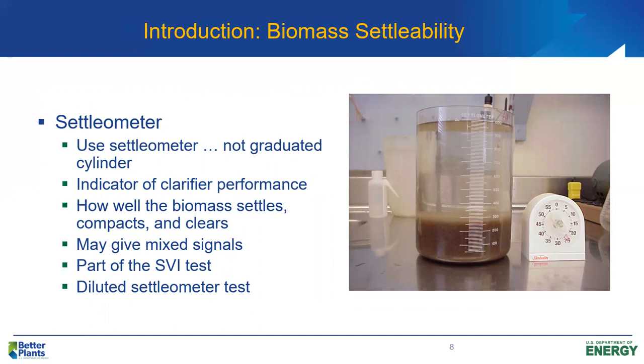If you were to ask me which single tool I'd choose to operate an activated sludge plant, I'd say give me a settleometer and I could probably do a reasonably good job. Obviously we want to use all the tools in our toolbox — like a doctor who should run whatever tests are needed, not just one. But the settleometer test is really valuable. It tells us a lot about how the process is performing: how the sludge is settling in the final clarifier, how the sludge is compacting, what our supernatant looks like. It also allows us to calculate the SVI — the sludge volume index — by taking the 30-minute settleability value in mL/L, dividing by the grams per liter of mixed liquor suspended solids, giving us SVI in milliliters per gram.